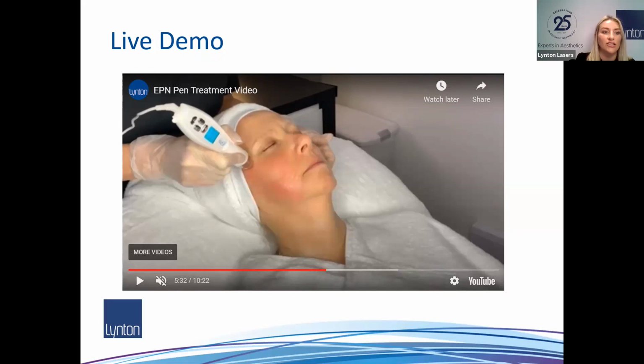Natalia's asked an interesting question. There are new regulations coming out at the end of the year. Is it approved? We're actually questioning whether that change in law is going to happen now because of Brexit, because it was a question about whether or not that will actually come into play. But if it does, then yes, it will be compliant with the new device regulation, the MDR, rather than just the directive.